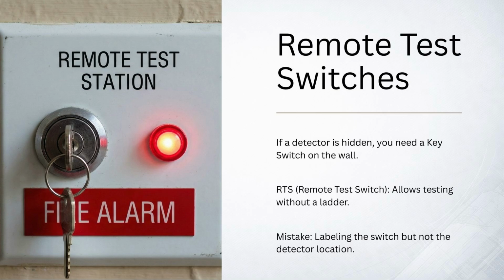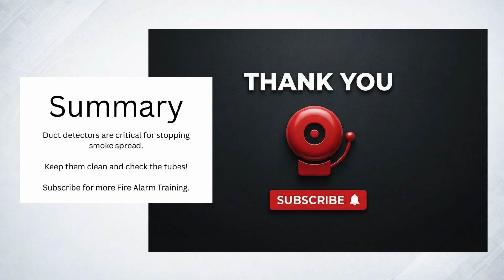But the most important part of the test isn't the alarm, it's the shutdown. When that red light comes on, you must visually verify that the HVAC fan has stopped spinning. If the alarm sounds but the fan keeps running, the system has failed. Duct detectors are a pain, but they save lives by preventing smoke from spreading. If you take the time to check the tube orientation, measure the pressure, and keep them clean, they will work reliably.